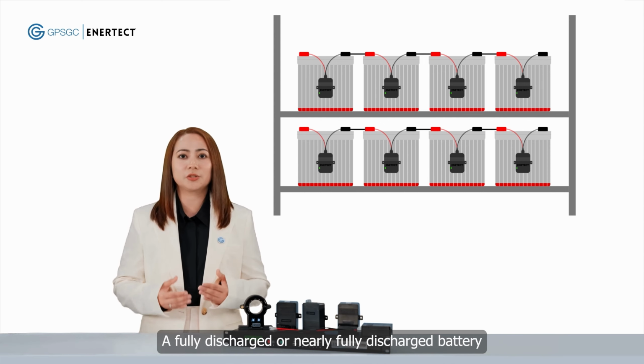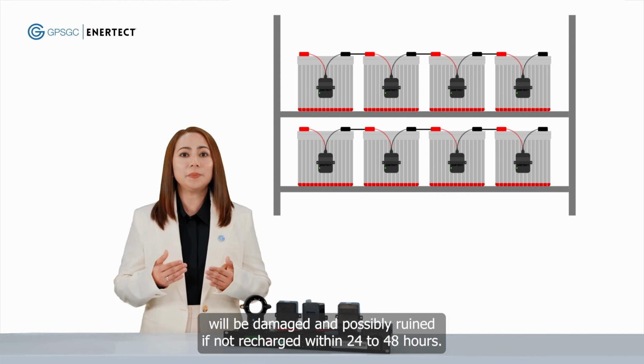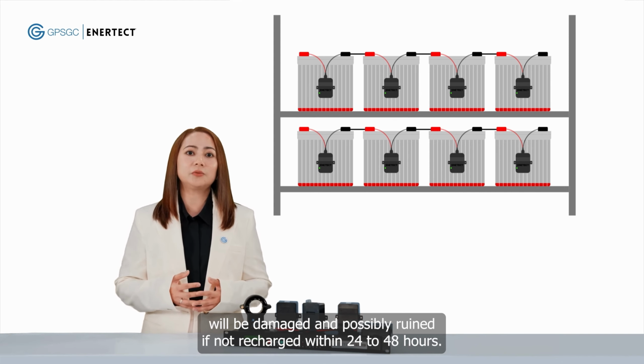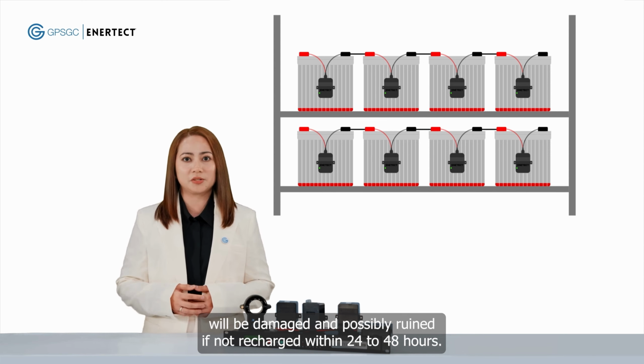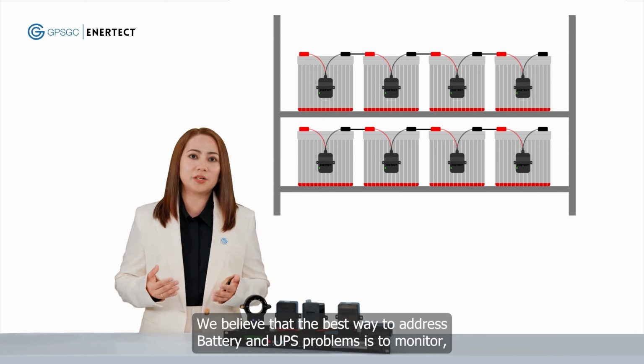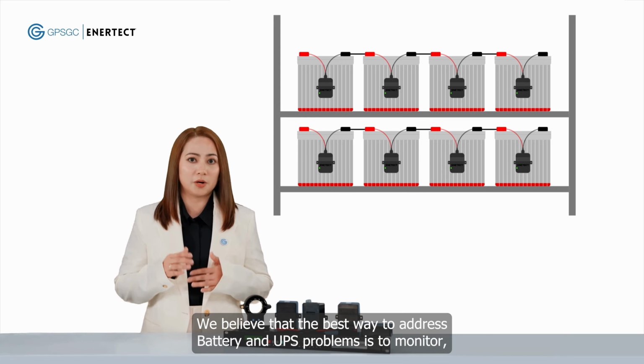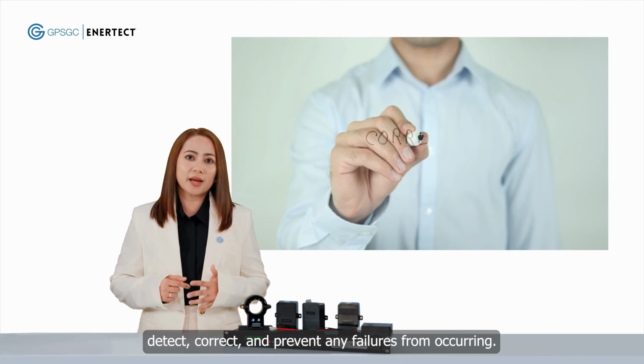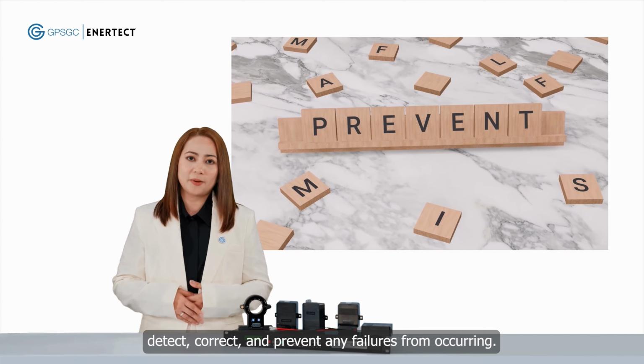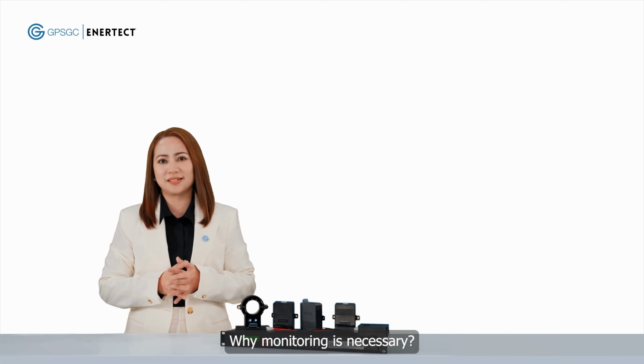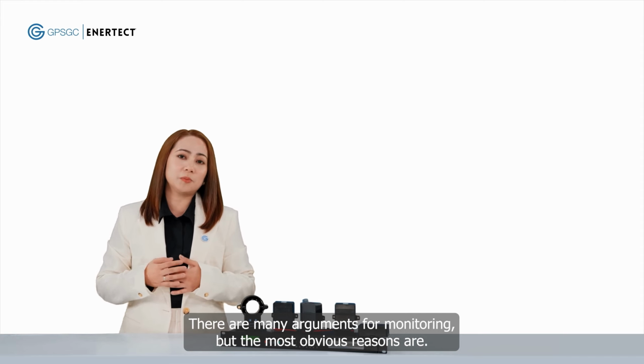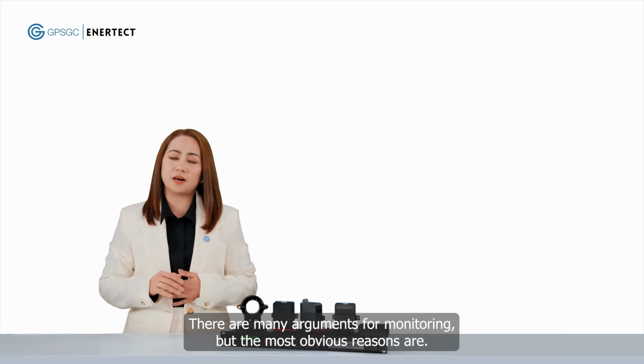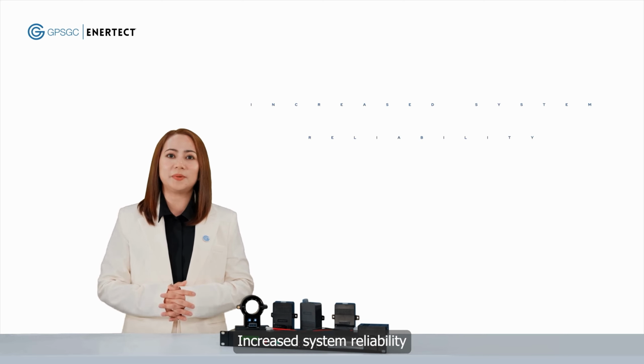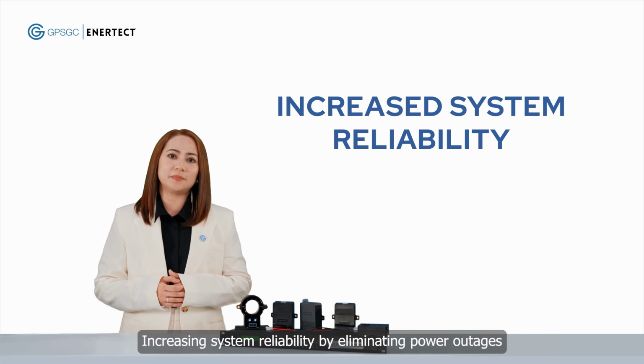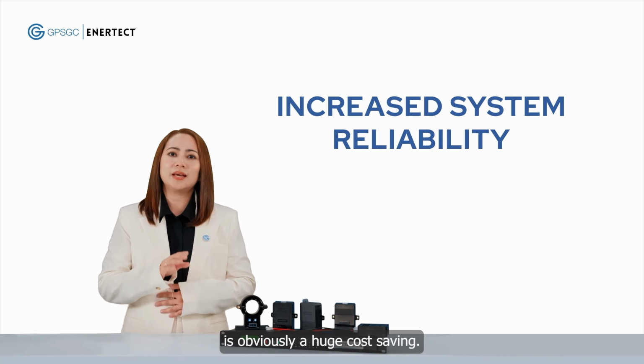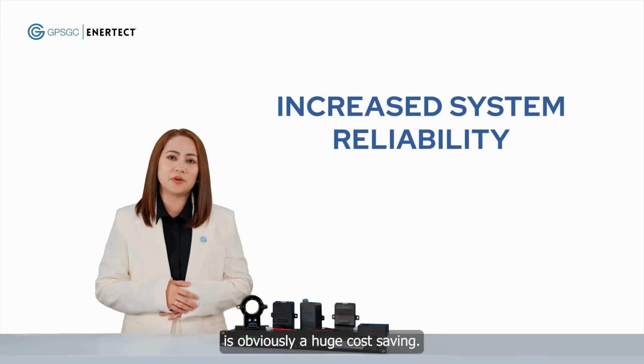A fully discharged or nearly fully discharged battery will be damaged and possibly ruined if not recharged within 24 to 48 hours. We believe that the best way to address battery and UPS problems is to monitor, detect, correct, and prevent any failures from happening. Why monitoring is necessary? There are many arguments for monitoring, but the most obvious reasons are increased system reliability. Elevating system reliability by eliminating power outages is obviously a huge cost saving.